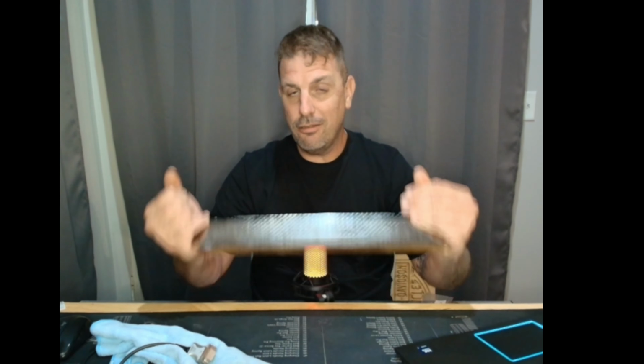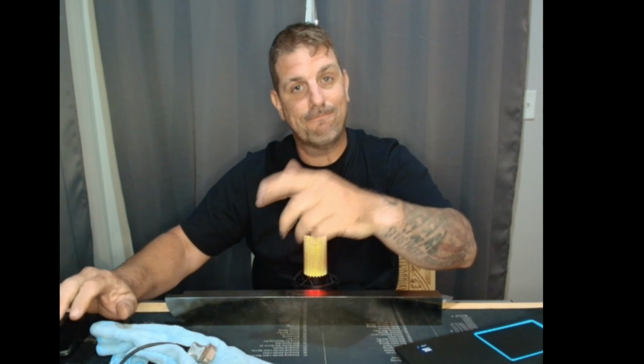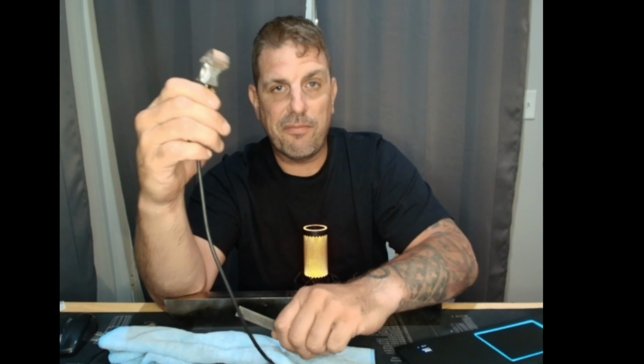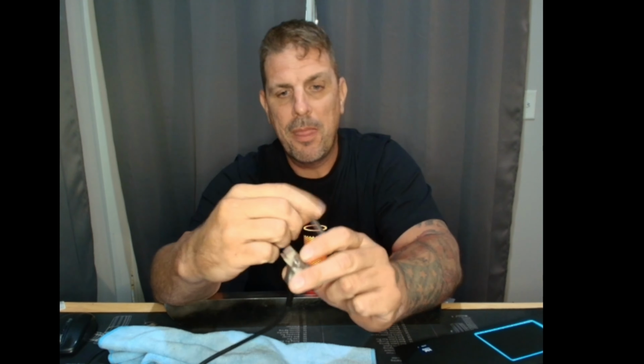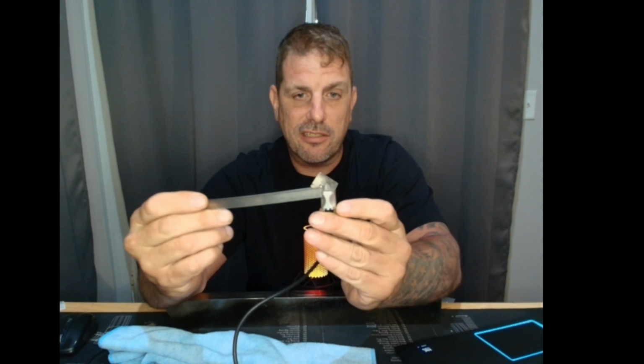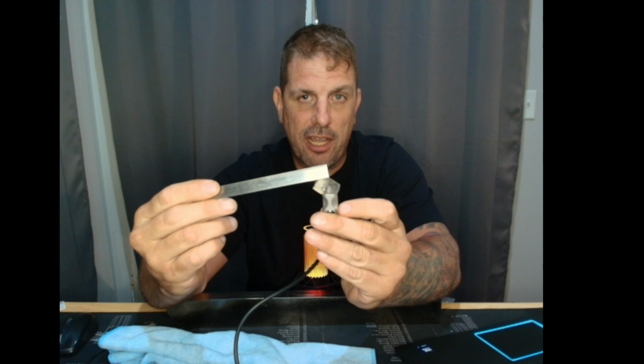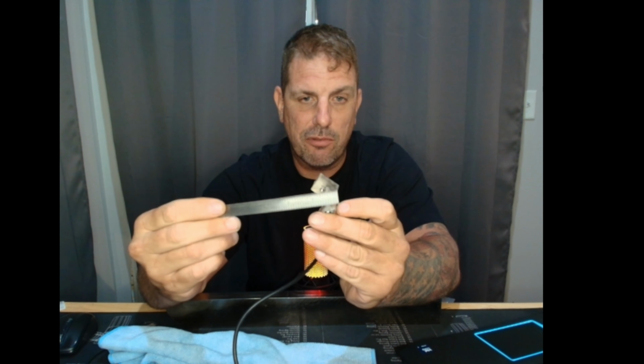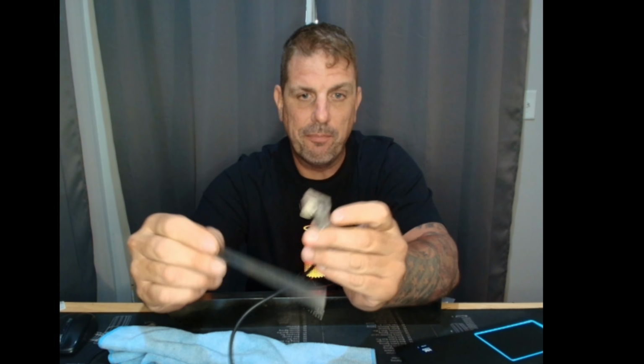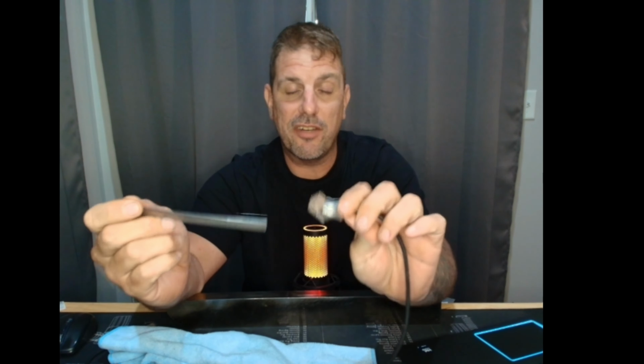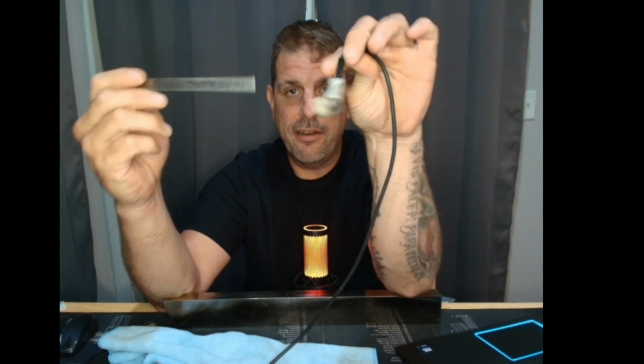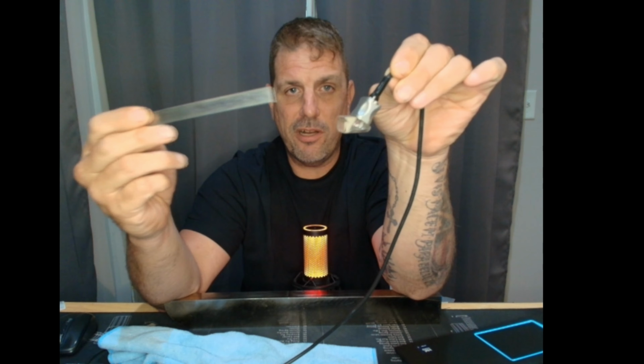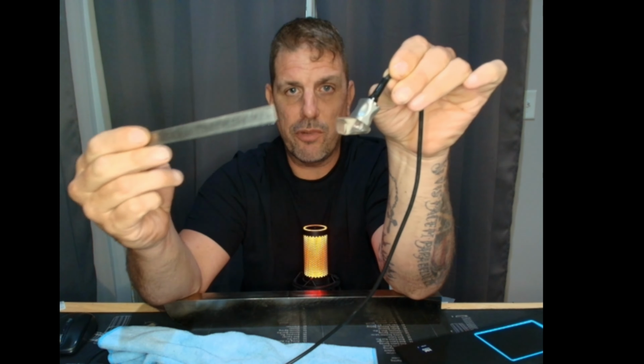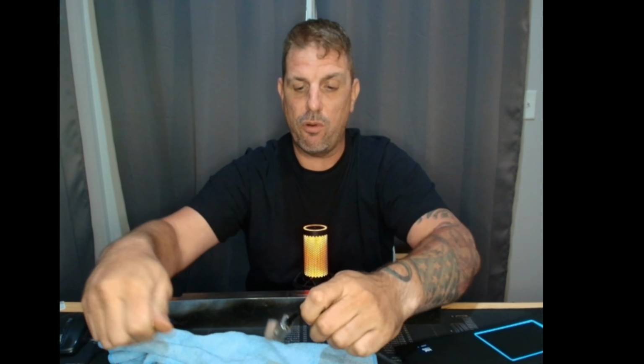So today we're going to walk you through calibration. Let's check it out. We're going to use a 5L16 probe with an SA10 N55S wedge. We're going to calibrate the distance of the wedge to the angles, 45 to 70. So we're going to calibrate wedge delay, and then we're going to calibrate sensitivity. Sensitivity is going to put our marker at how far in front, how far down. So we're going to set up that way it grids it out for us.